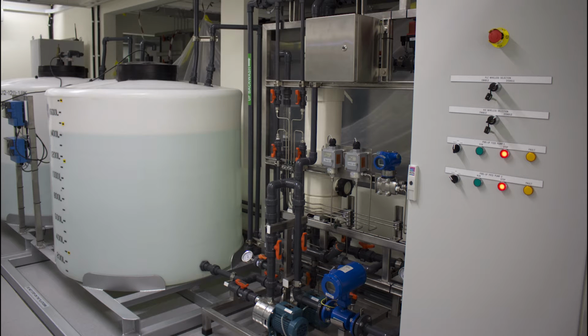This is stage 3, the ultrafiltration stage. The PLC at this stage turns this pump on to move water from tank 301 through this UF or ultrafiltration unit to tank T401. The ultrafiltration unit contains a large number of micrometer membranes to remove solid matter from incoming water. This stage contains several motorized valves to control the flow of water into and out of the ultrafiltration unit, as well as sensors to measure pressure values.